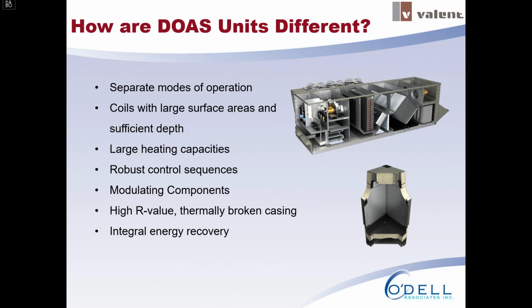And then the cabinet construction is going to have a thermally broken casing. We want to have that unit be very well insulated, have a high R value, and be of sound construction so that it'll last and handle that wide range of conditions. And finally, what you'll see on a lot of DOAS units is some form of energy recovery. If you're bringing in high amounts of outside air, chances are you're exhausting air at some point. And if you can bring that exhaust air through the unit, why not recover some of that energy to make your system more energy efficient? You could actually reduce the amount of heating or cooling load that your unit does just based on the amount of energy that you're able to recover. So these are all key differences and things to think about when you're designing a DOAS unit.